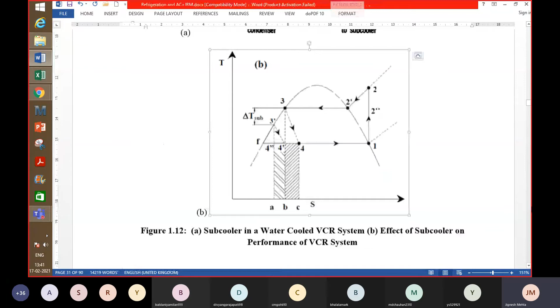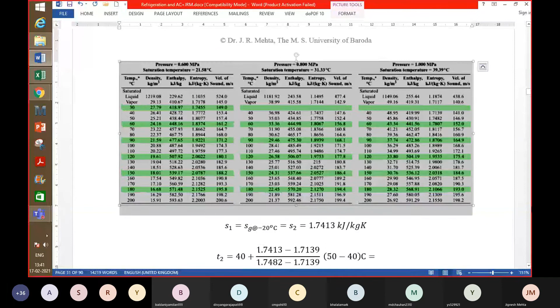Probably I can go to that chart. So this is as per the standard cycle. Now here the temperature is 39 or almost 40, 39.39, as you can also read from here, right? Now you don't stop here, but you extend this line up to this 30-degree line. You go horizontally up to this point, and then you draw a vertical line, and then your evaporation starts, right? So the length of the evaporation process inside the saturation dome has increased. That is one thing. And you are providing a little more cooling, so obviously there is more heat rejection in the condenser.